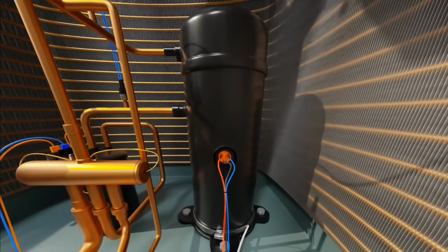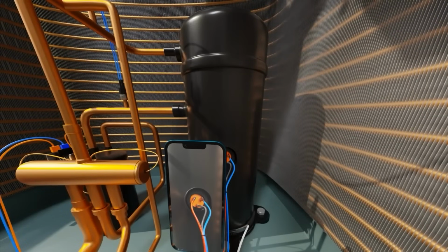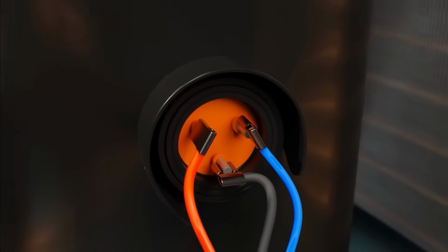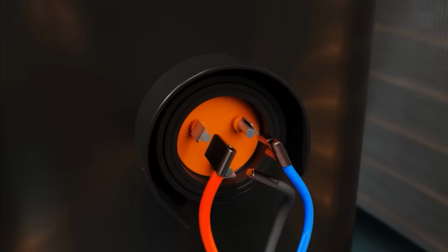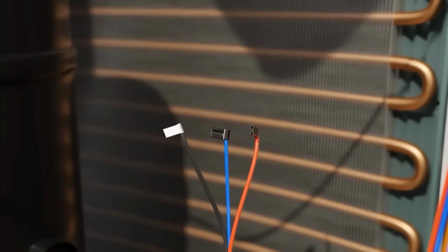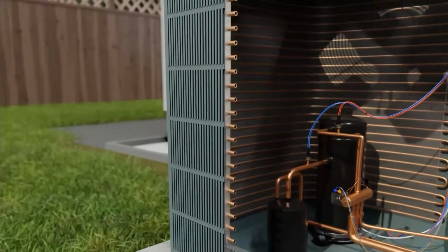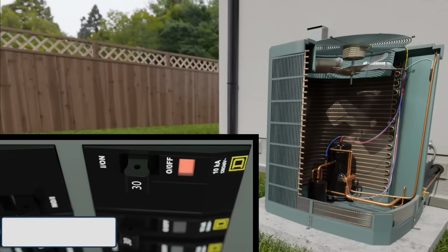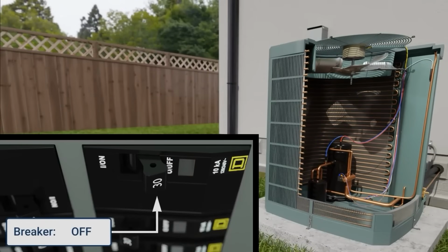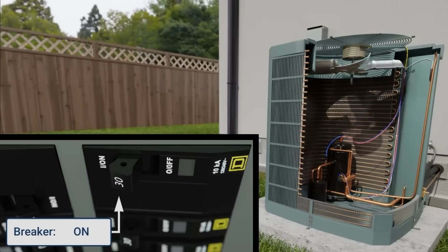What I want you to do is take the plug off the compressor or the terminals. If you have terminals, take a picture so you can put them back on correctly. Take them off, isolate them, put them to the side so they can't short on anything. Put the top back on, flip the breaker on. Now if everything else works with the compressor isolated out, you've proven your hypothesis that it was the compressor that was shorted, so you've eliminated it.